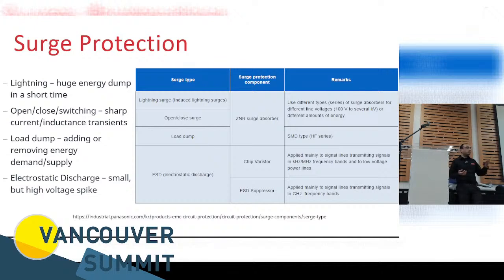You've got to remember that if you remember your CRT TVs with the old antennas, they look like clothes racks. Your PV array is one giant clothes rack. It's like the old TV antenna, waiting to pick up lightning strikes. So anytime you've got a very big PV array connected to an inverter, the bigger the array, the greater the likelihood that you're going to draw something into it because of the mesh of wires you've got. It's like a Faraday cage. So the more protection you will need for that.